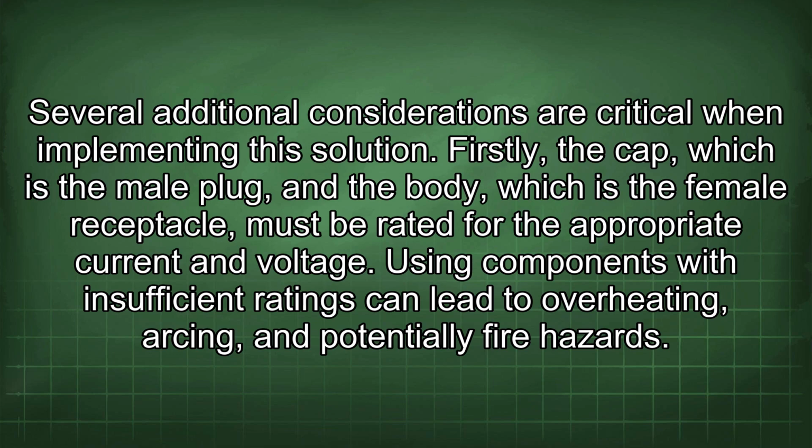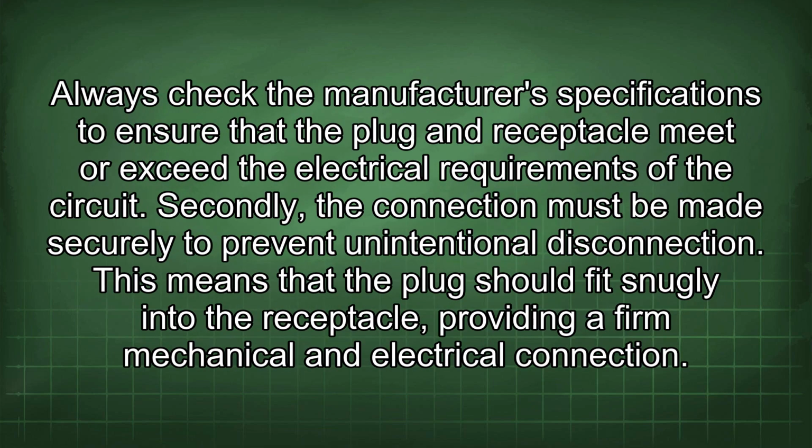Several additional considerations are critical when implementing this solution. Firstly, the cap, which is the male plug, and the body, which is the female receptacle, must be rated for the appropriate current and voltage. Using components with insufficient ratings can lead to overheating, arcing, and potentially fire hazards. Always check the manufacturer's specifications to ensure that the plug and receptacle meet or exceed the electrical requirements of the circuit. Secondly, the connection must be made securely to prevent unintentional disconnection.